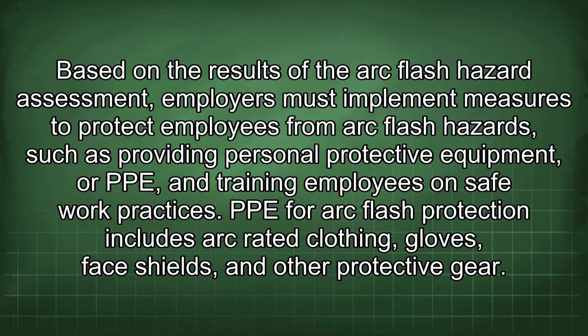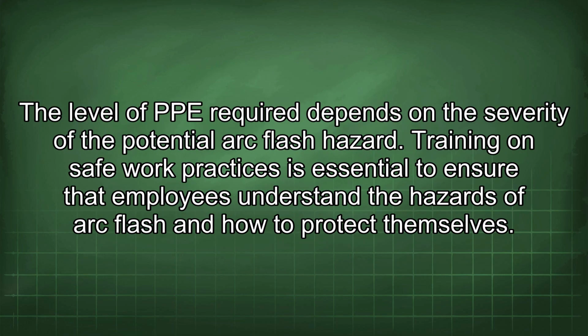Based on the results of the arc flash hazard assessment, employers must implement measures to protect employees from arc flash hazards, such as providing personal protective equipment, or PPE, and training employees on safe work practices. PPE for arc flash protection includes arc-rated clothing, gloves, face shields, and other protective gear. The level of PPE required depends on the severity of the potential arc flash hazard.